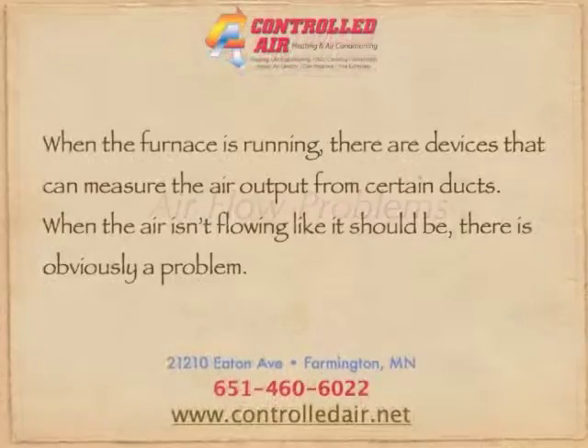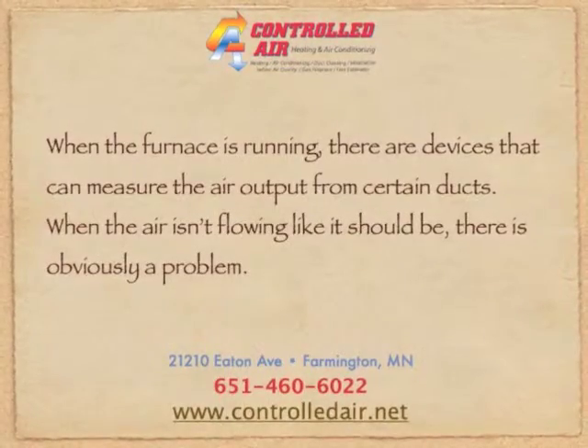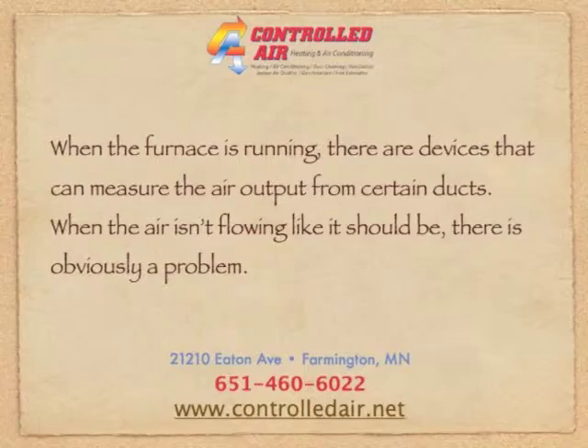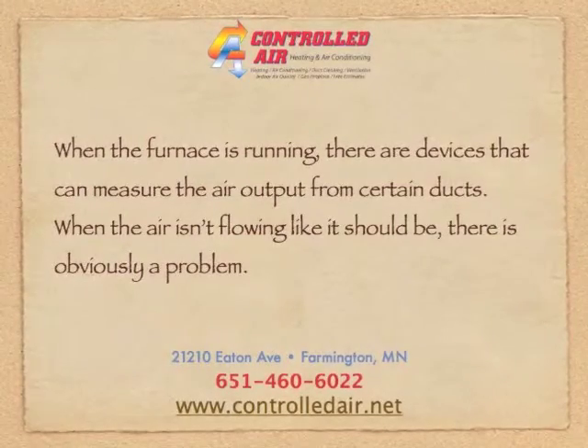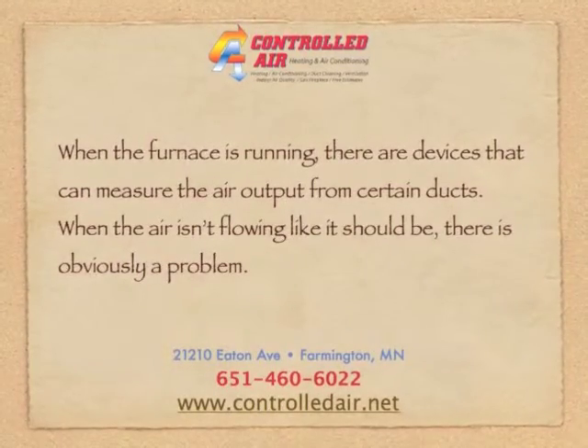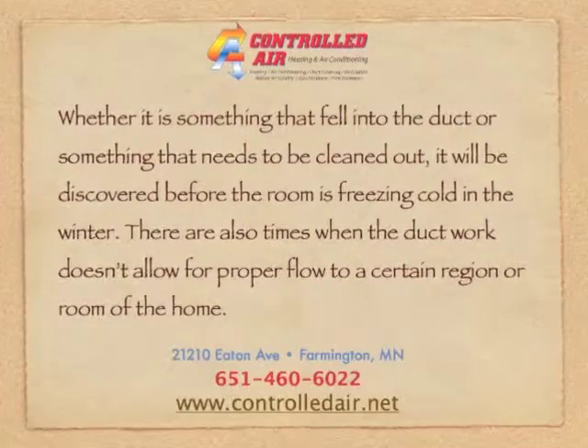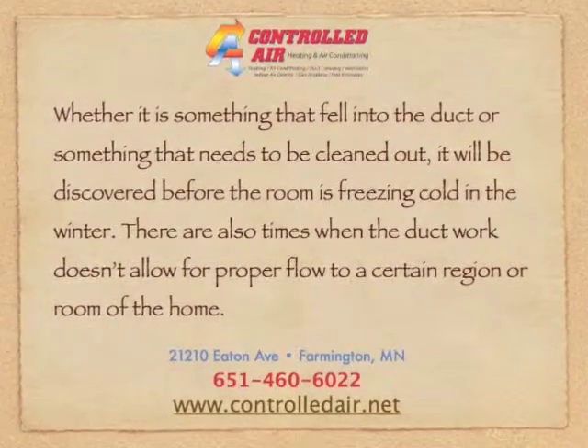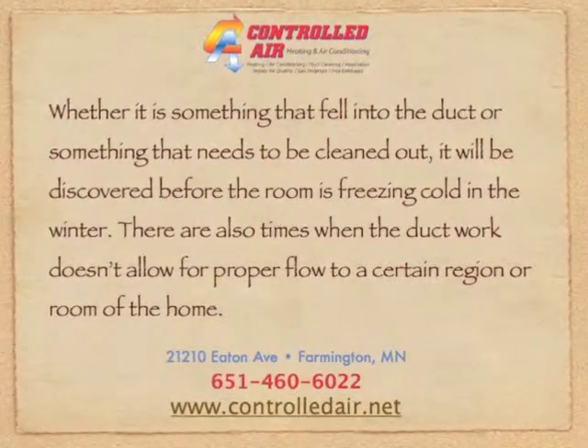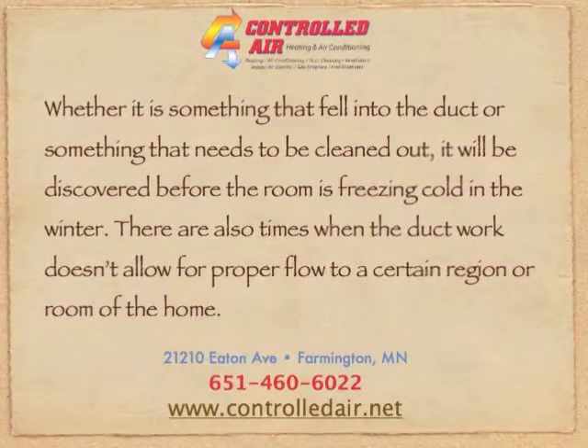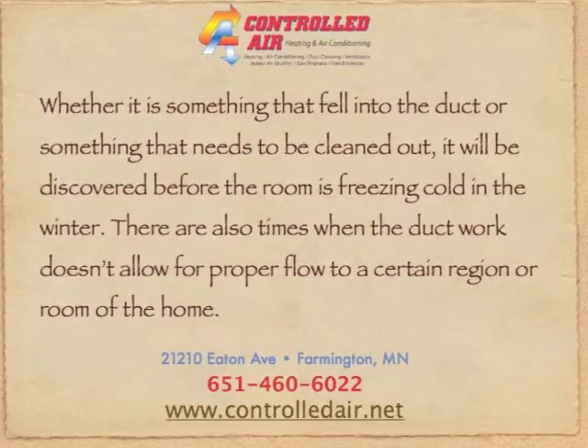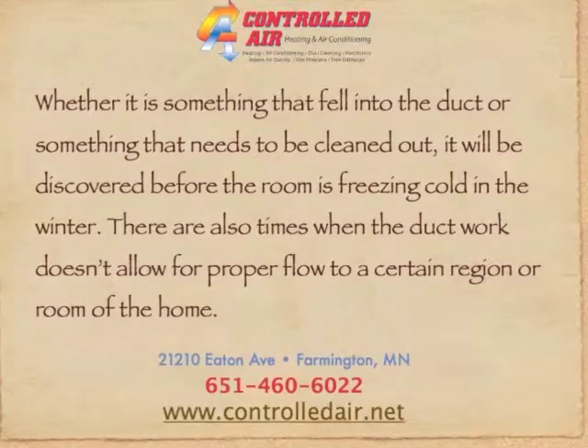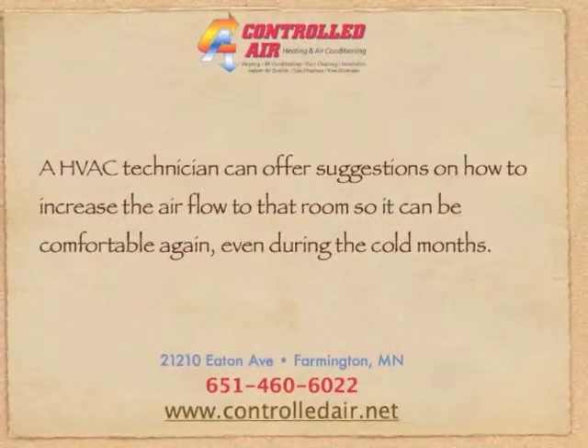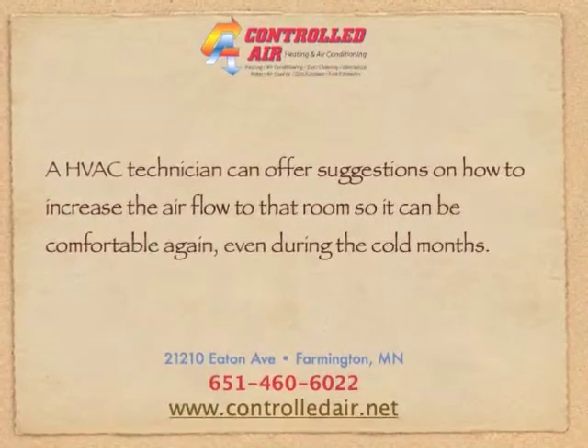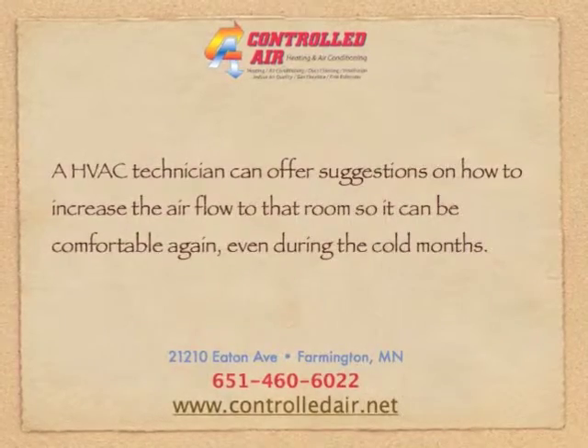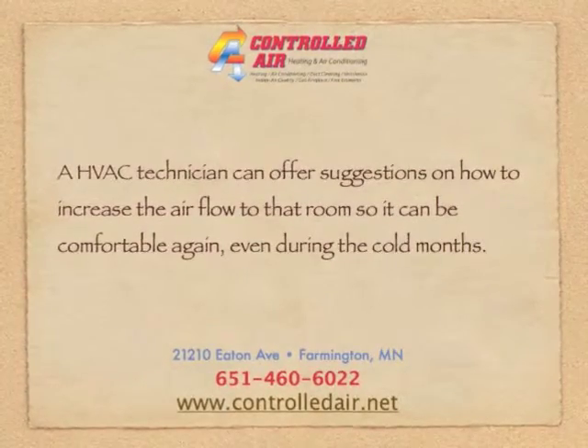Airflow problems are also checked—when the furnace is running, technicians use devices to measure air output from the ducts. If the air isn't flowing properly, there's clearly a problem, whether something fell into the duct or it just needs cleaning, and it can be found before a room turns freezing cold in winter. Sometimes the ductwork itself doesn't allow proper airflow to a certain room. An HVAC technician can offer suggestions to improve airflow to that room so it stays comfortable even during the cold months.